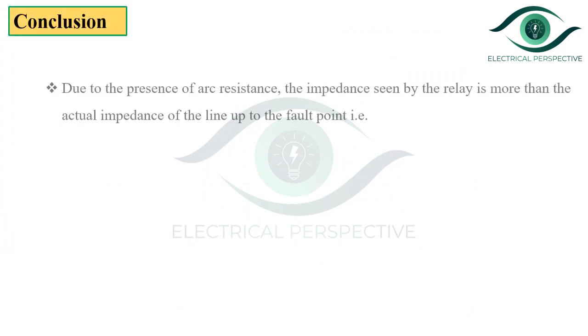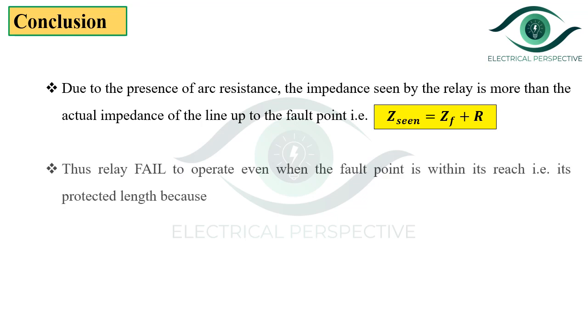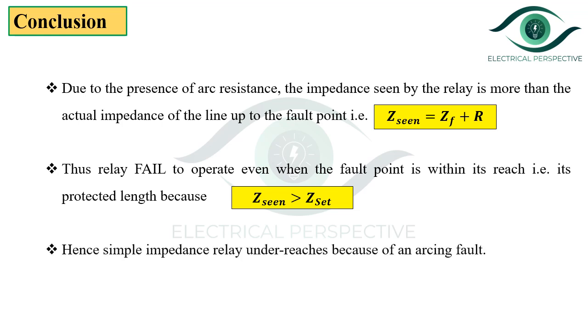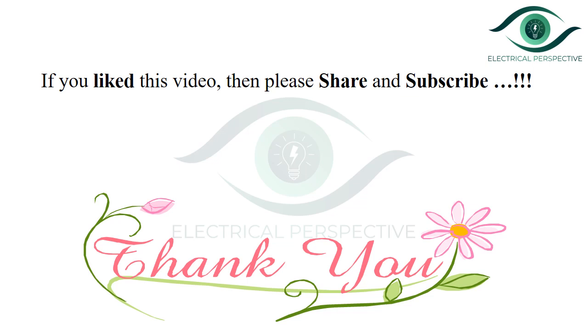These are the conclusions. Due to the presence of arc resistance, the impedance seen by the relay is more than the actual impedance of the line up to the fault point — that is, Z_seen = ZF + R, where R is the arc resistance. Thus the relay fails to operate even when the fault point is within its reach, because Z_seen is greater than Z_set. Hence the simple impedance relay under-reaches because of the arcing fault. If you like this video, please share and subscribe. Thank you.